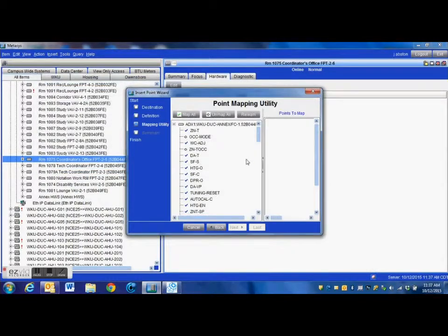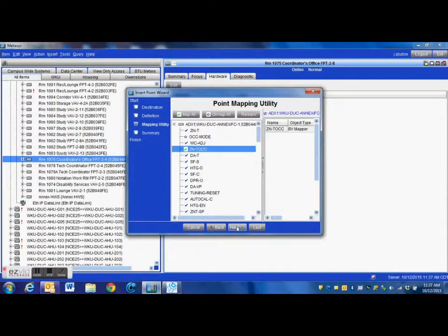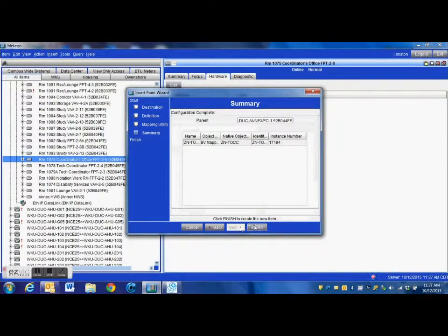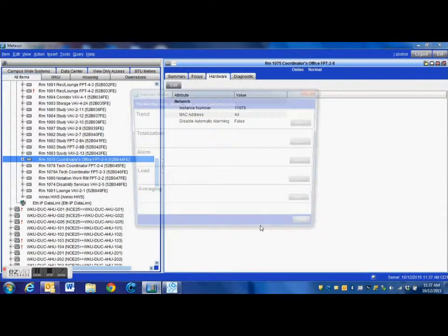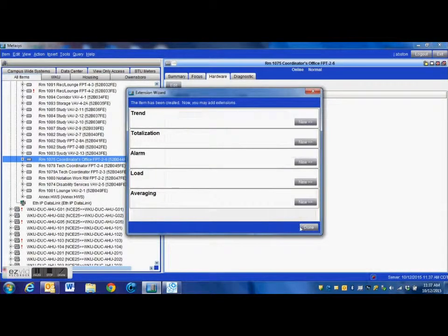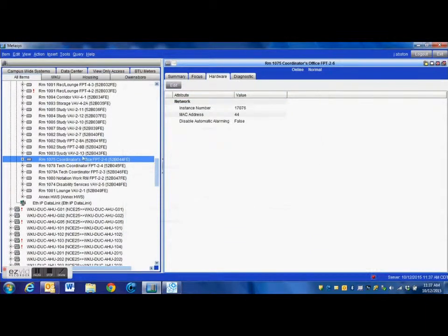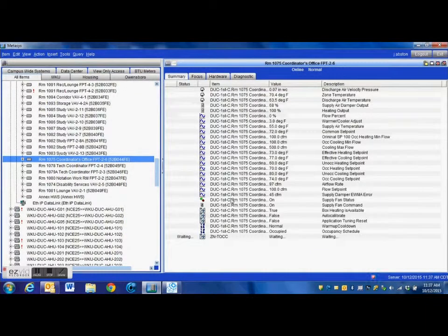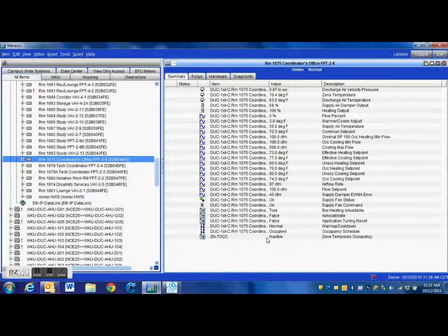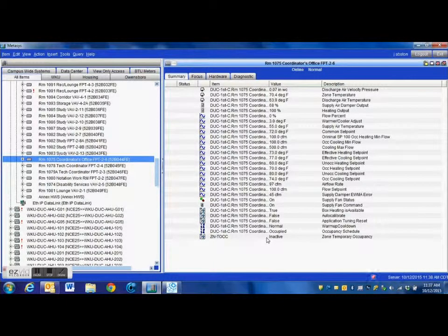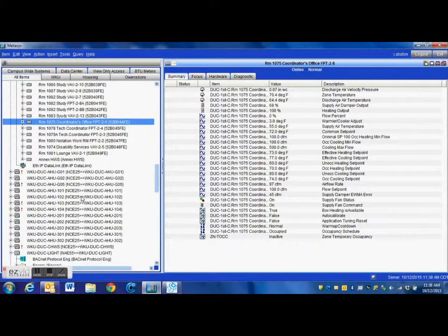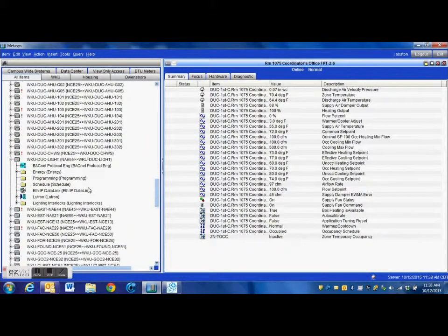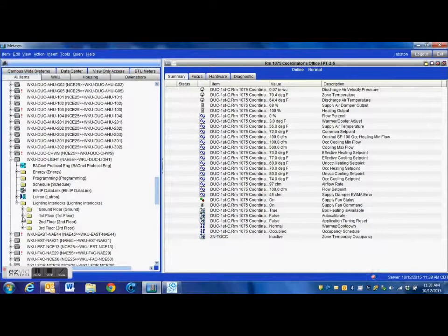It takes a couple minutes to scan. I'm just going to close this window. Here is the point that I want, so I'm going to double click that and hit next and hit finish. I do not want to add any trends or alarms, so I'm just going to hit done. Now when I double click on my controller, I can see the point here. The two states of this are active and inactive. Currently it is inactive, but if I were to press that button it would go active and that's what we want.